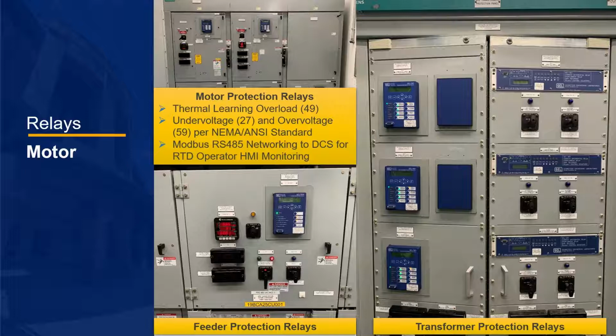Included as well is an RTD biased trip set based on manufacturer nameplate ratings. In addition, the RTD data is monitored via the plant distributed control system via added daisy chain Modbus connections. Each MCC section has a dedicated connection to the DCS in lieu of each relay, saving on space and installation costs. This allows the client to monitor all motor temperatures from the control room and track trends.